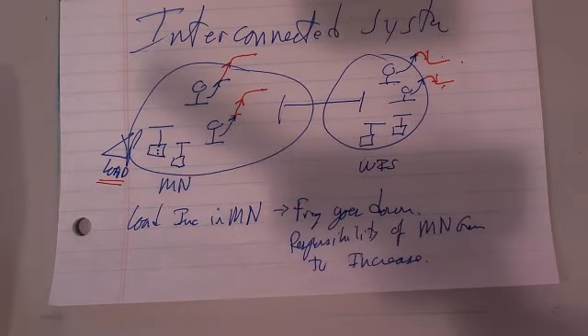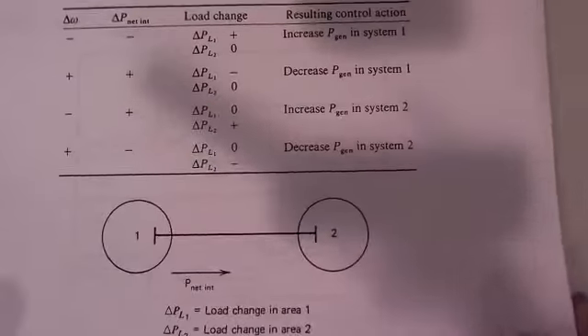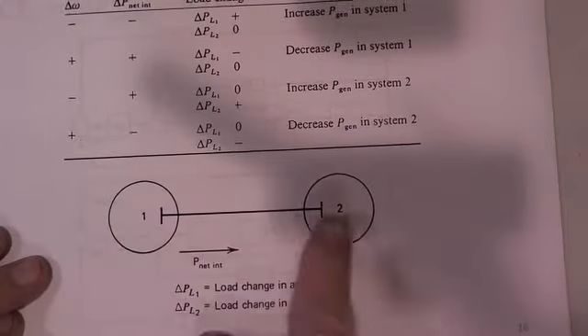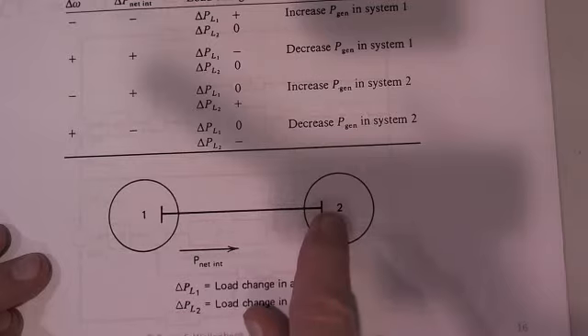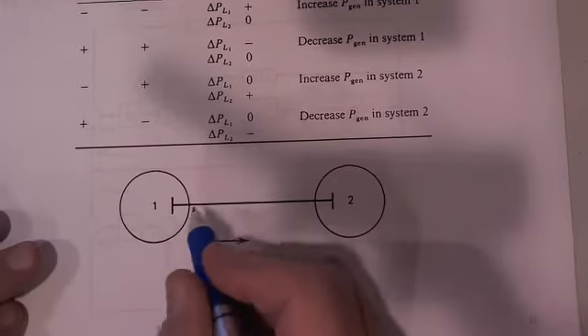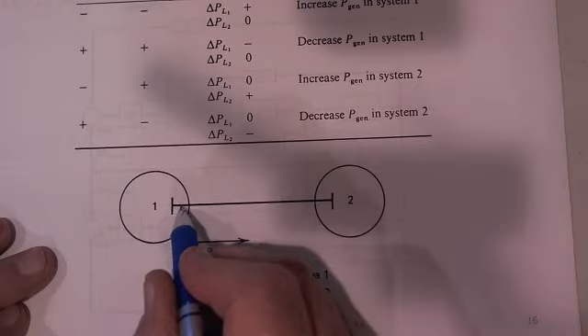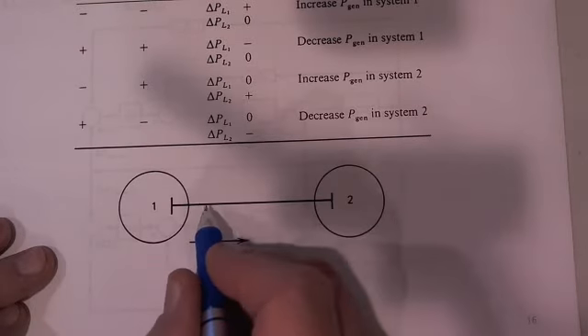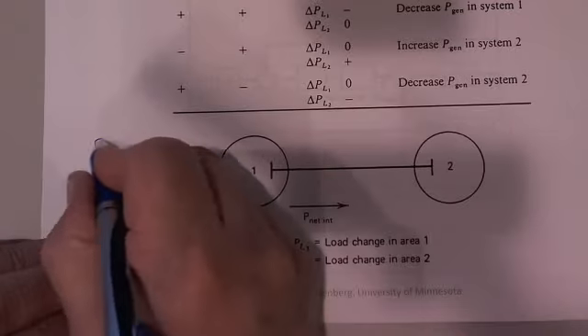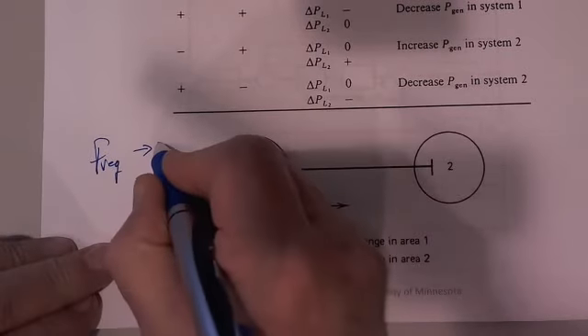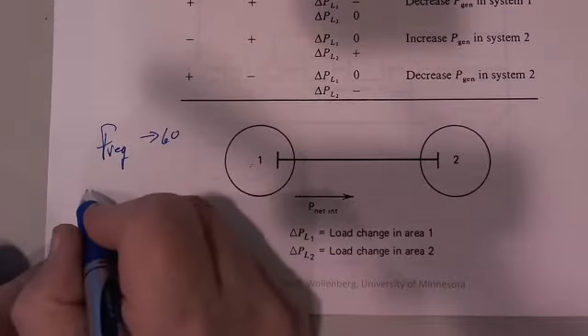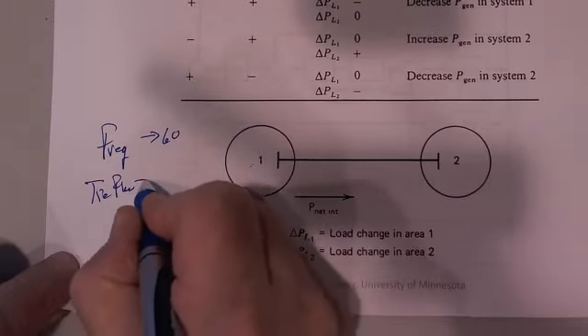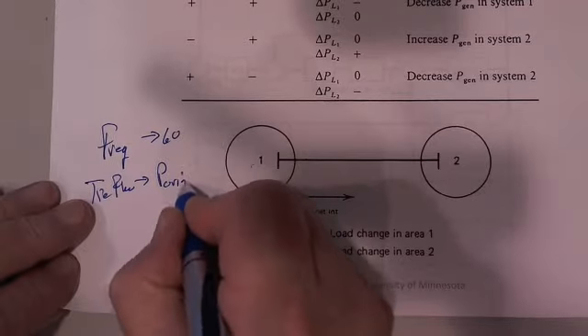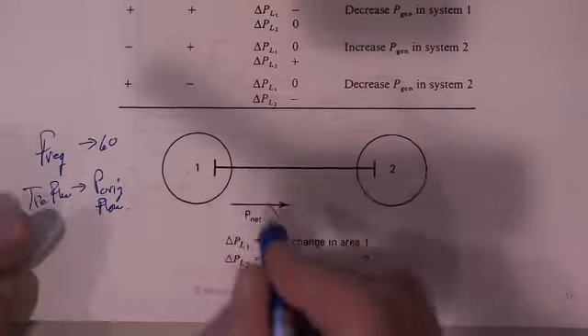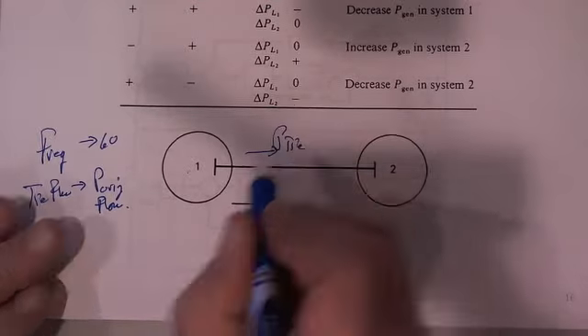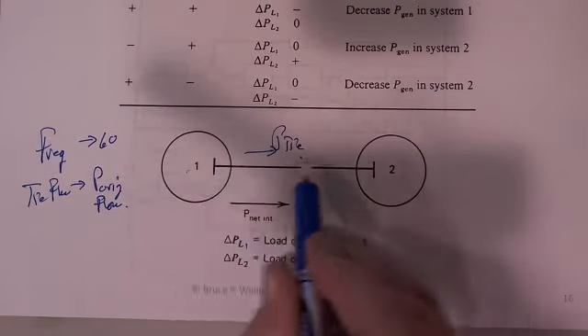And we're going to talk about the fact that if I have generators in two different areas and I have a tie line, I want to control the tie line flow so that after a load event, frequency goes back to 60 and tie flow goes back to the original flow. Here's P tie. That goes back to the original, and the frequency goes back.